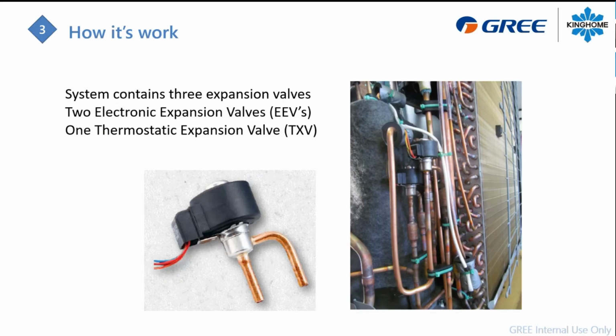Also, in those systems, you will have those kinds of EEV. So we saw on the diagram, you have EEV1 and EEV2. And also in the indoor unit, you will have your TXV. So you will have 2 electronic expansion valves and 1 thermostatic expansion valve. In these kinds of valves, you have a magnet inside, and you have this electronic magnet over it, so the head over the body right here. This kind of valve will rotate, and you have a small needle inside of it.